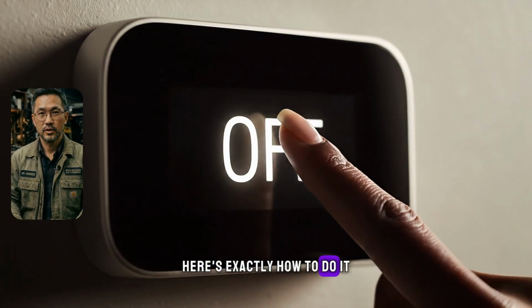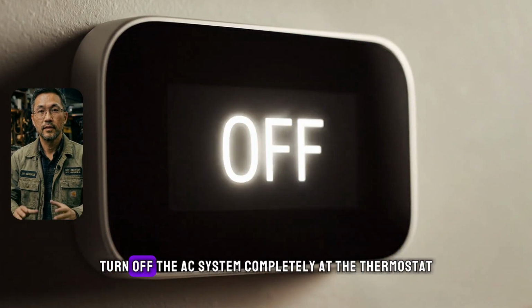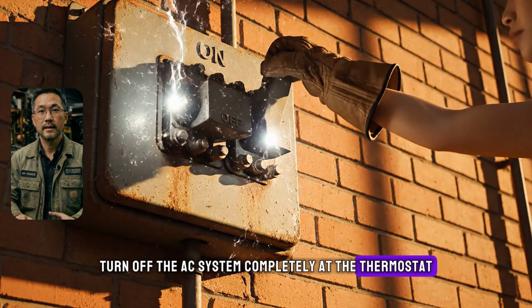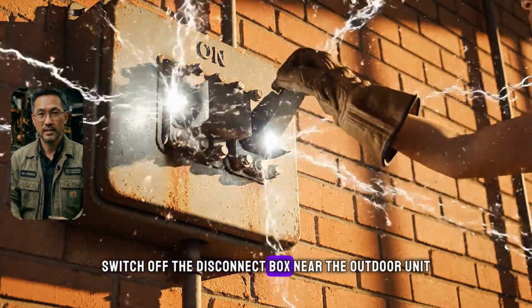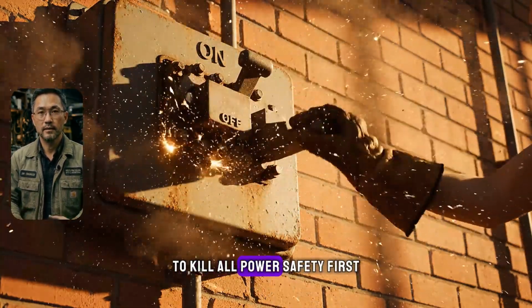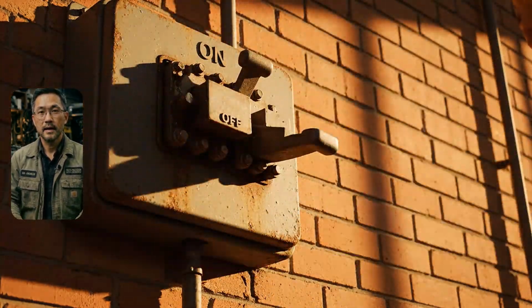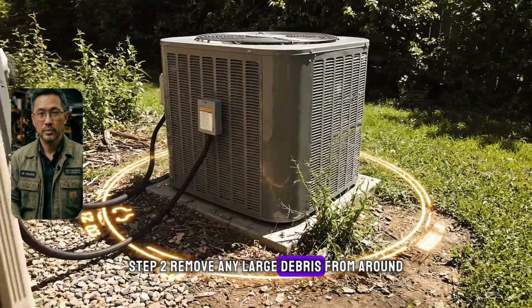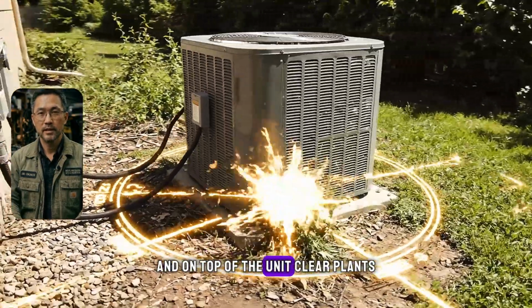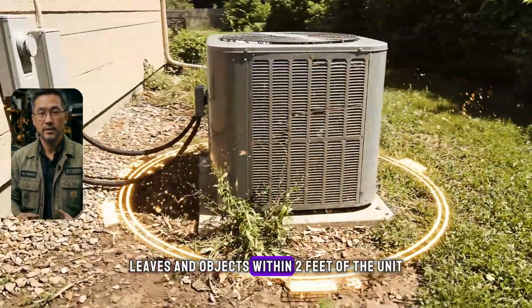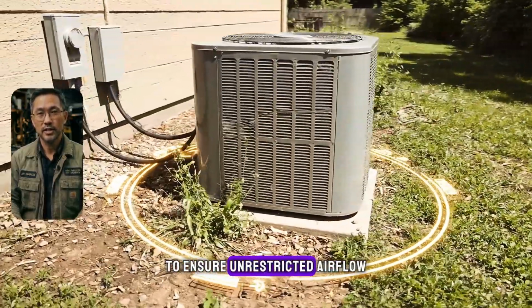Here is exactly how to do it. Step 1. Turn off the AC system completely at the thermostat. Then switch off the disconnect box near the outdoor unit to kill all power. Safety first. Step 2. Remove any large debris from around and on top of the unit. Clear plants, leaves, and objects within 2 feet of the unit to ensure unrestricted airflow.